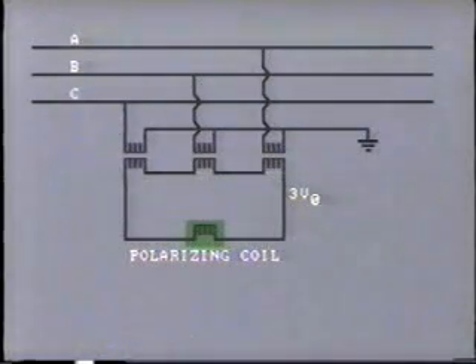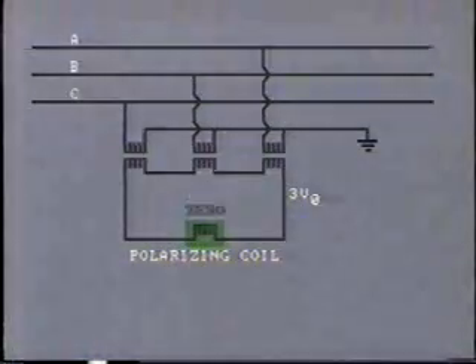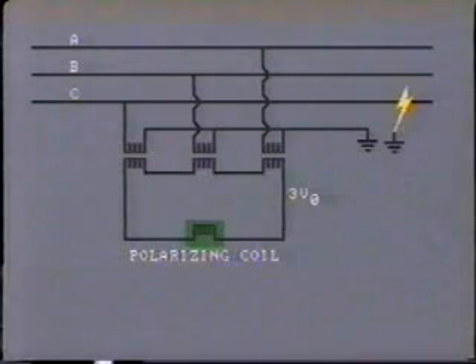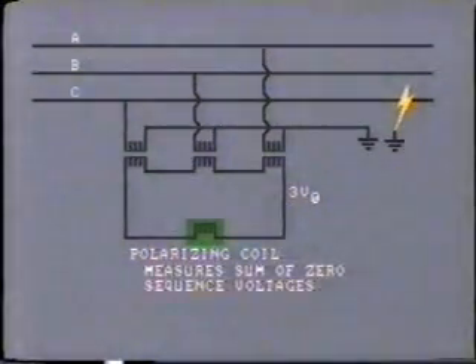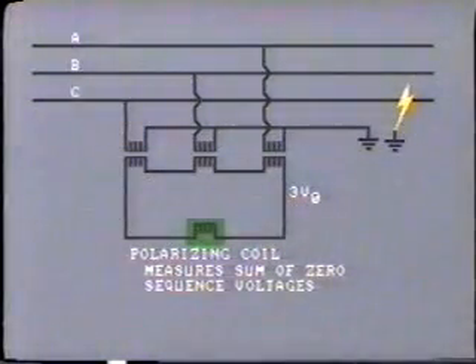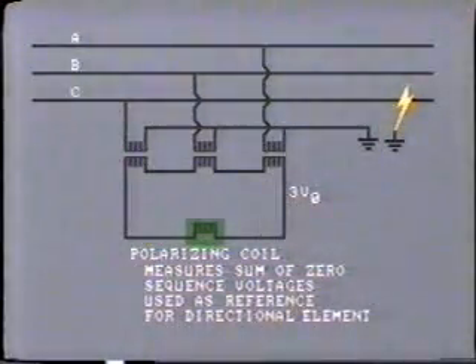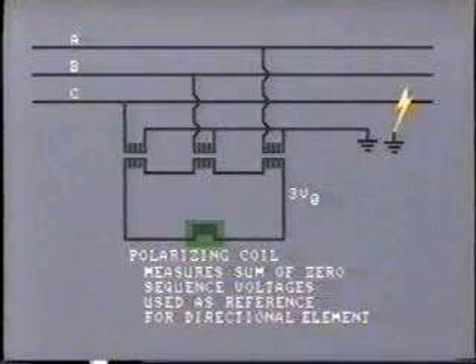When there is no fault on the line, the sum of the voltages in the secondary will be 0, as the 3 phases balance out. However, when a ground fault occurs on one line, the voltage coil will measure the sum of the zero sequence voltages, which are caused by the out of balance. This can then be used as reference for the directional element. However, this method does have certain limitations and is therefore not always applicable.